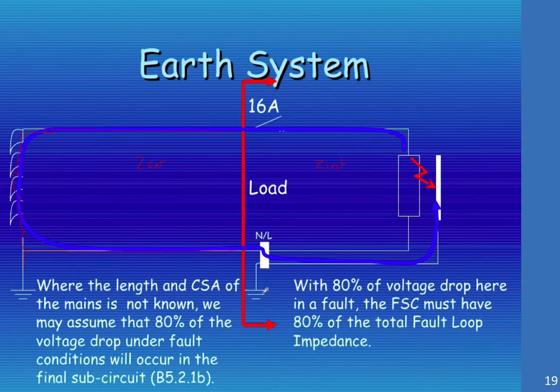Where the length and cross section of the mains is not known, we may assume that 80% of the voltage drop under the fault condition will occur in the final sub circuit. Basically we're saying we may not know what this is. Effectively we're assuming that the supply authorities will only limit the current by 20% with their transformer impedance.